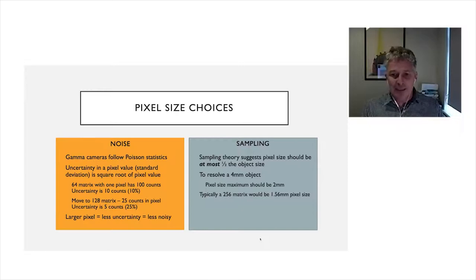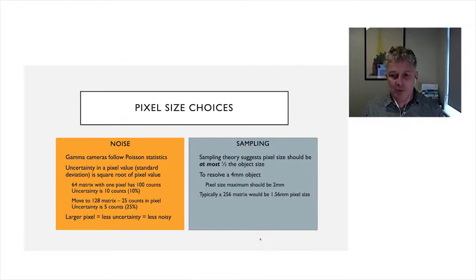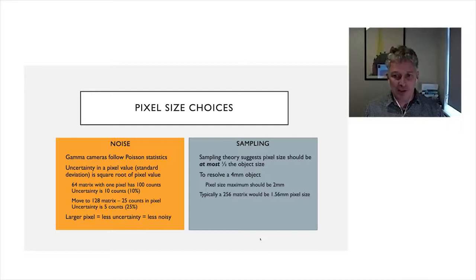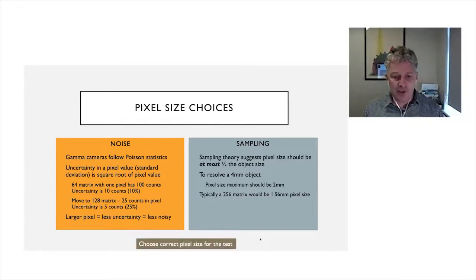Sampling theory dictates that pixel size should be at most half the object size. So if we were trying to resolve a four millimeter object, the pixel size should be two millimeters. For a standard gamma camera field of view, a 256 matrix gives a pixel size of 1.56 millimeters. So for intrinsic spatial resolution measurements around four millimeters, a matrix size of 256 or better is appropriate. Different tests will push you either towards reducing noise or towards improving spatial sampling.